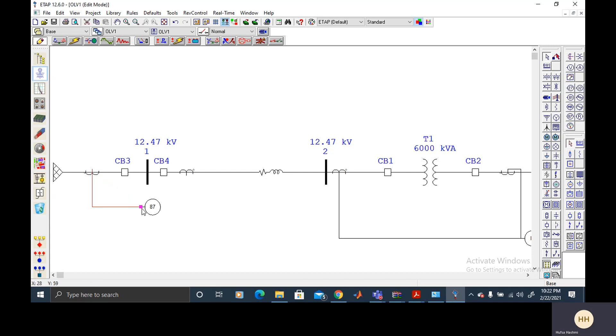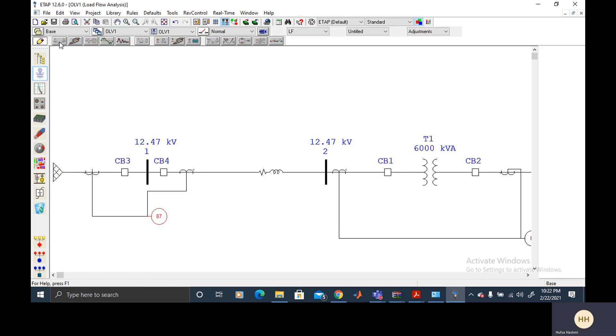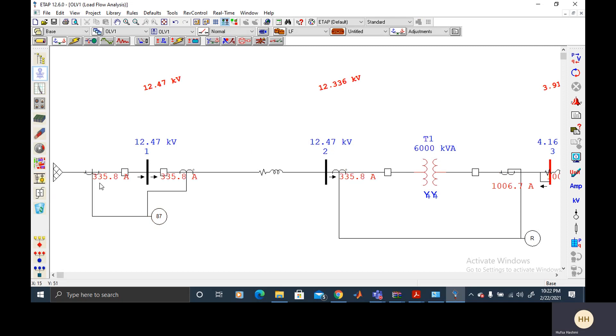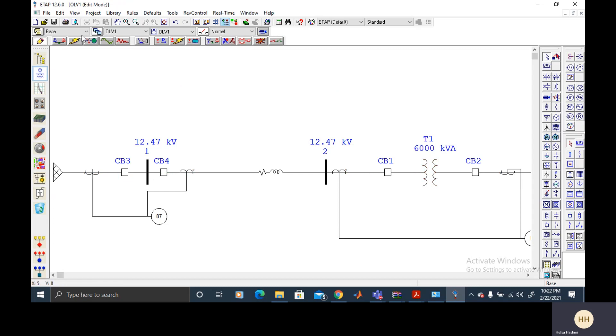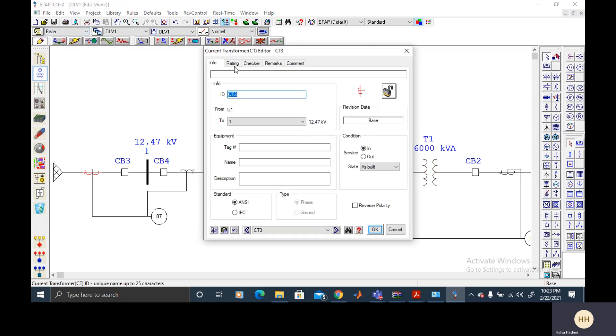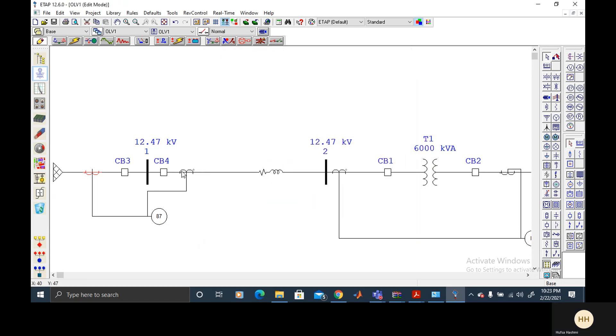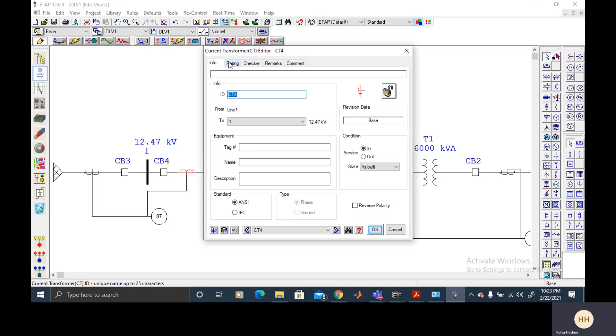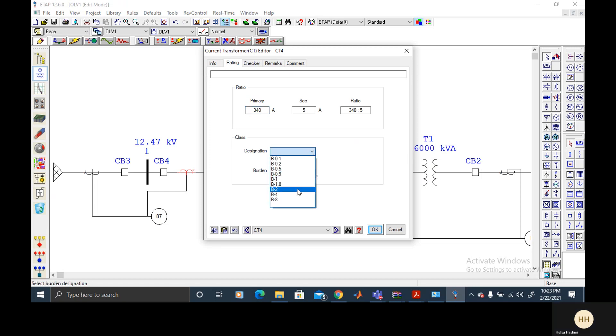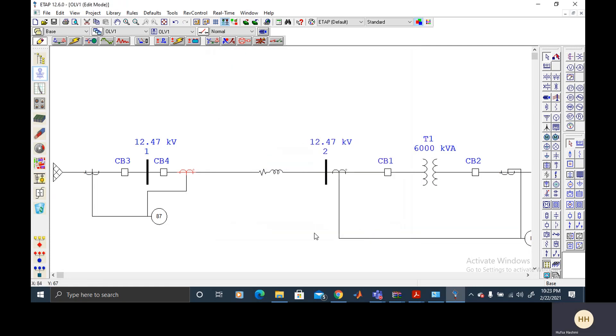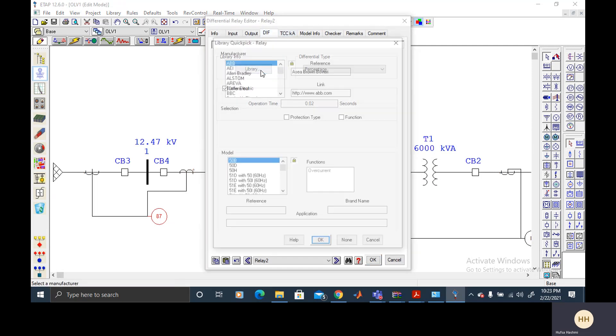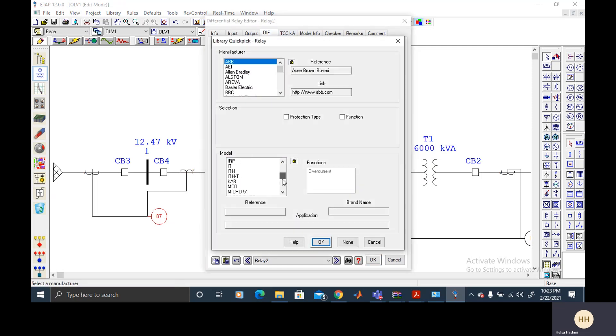And then two CTs. And then load flow analysis for the rating. From the analysis it has got 335 on either side. So now again switch to edit mode and select the rating as 340. And select class B2.